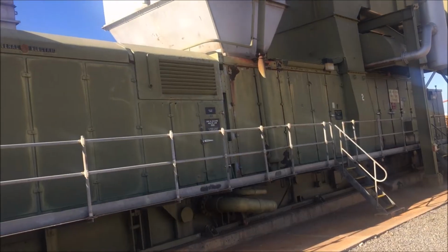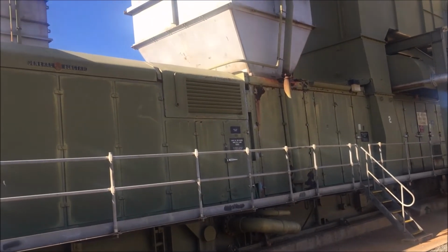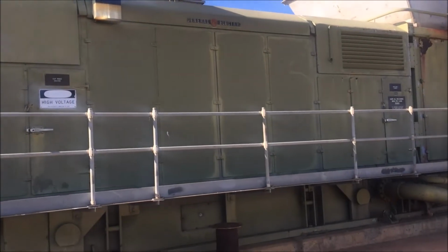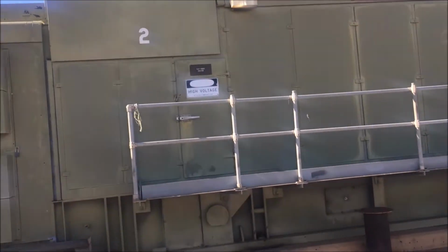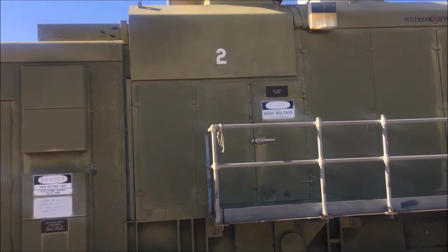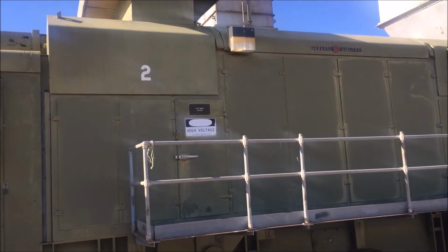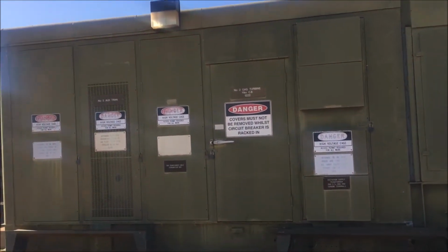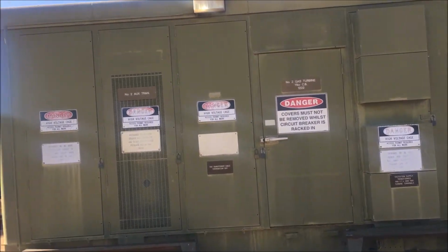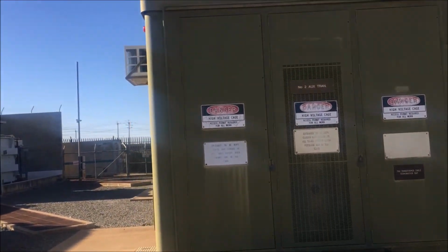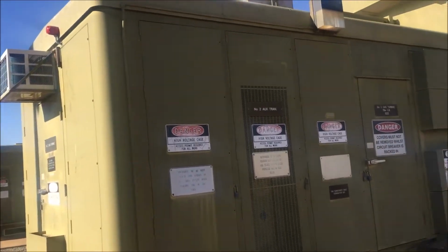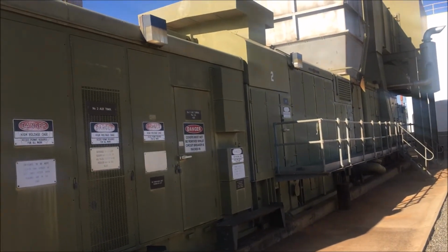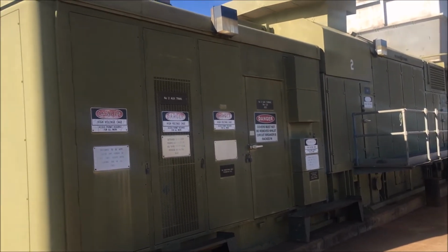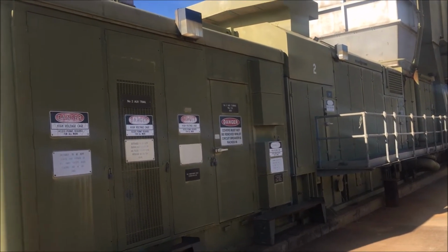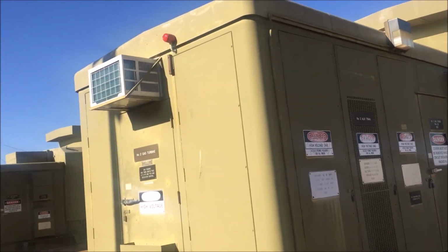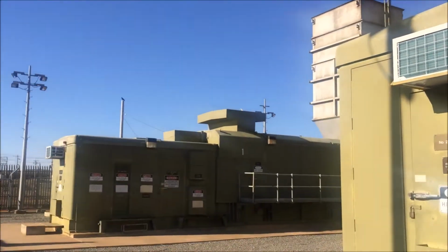The turbine spins at 5,500, I think. 5,000 something or other. And there's a gearbox about there which reduces to 3,000. And it's a 2-pole generator, so it gives you your 3,000, it gives you 50 hertz. And this part here, that's the circuit breaker going out, and that's the excitation control room in there. It's the GE American stuff, so all the voltage is American. We've had to put transformers in that go from 415 to 380. I don't know why they do 380, but that's American for you. So yeah, that's the turbine, and there's his mate over there.